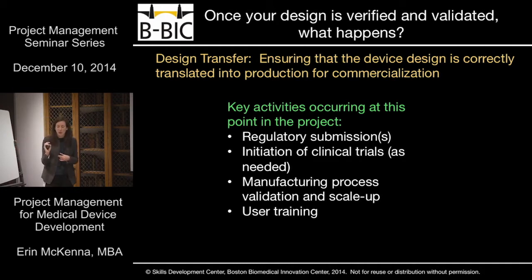Usually at about this point in a project for medical devices, this is the point that you would be submitting to regulatory agencies. They typically want to see you get through most of the design elements. They don't necessarily need to see you get through transfer, but they want to see the outputs. They want to see how that's going to work. And they also want you to talk about where you're going to be manufacturing and what are those elements. But they don't necessarily need to see, here's the entire manufacturing process. Here's all the manufacturing procedures.